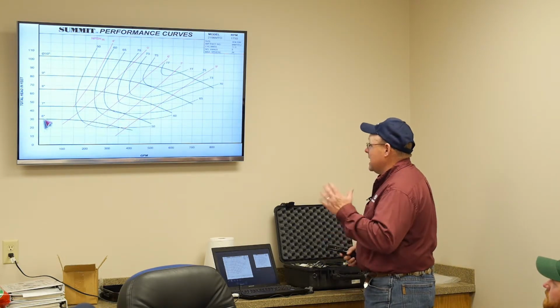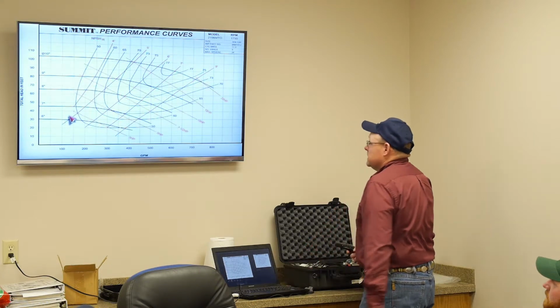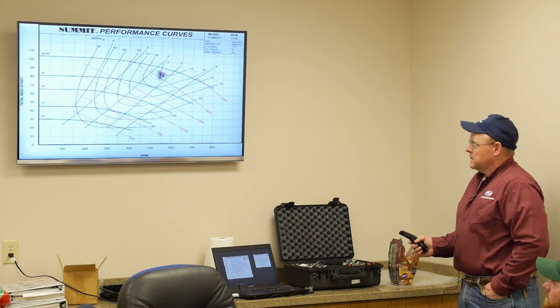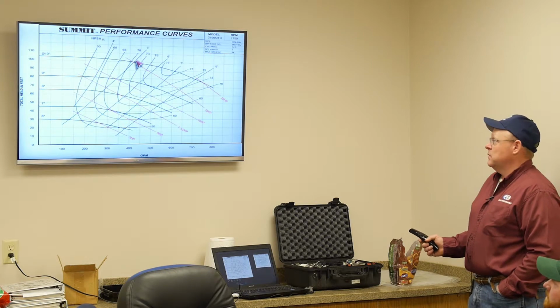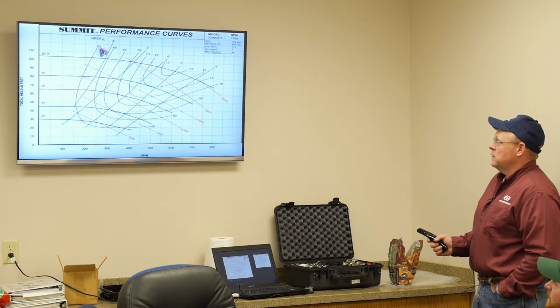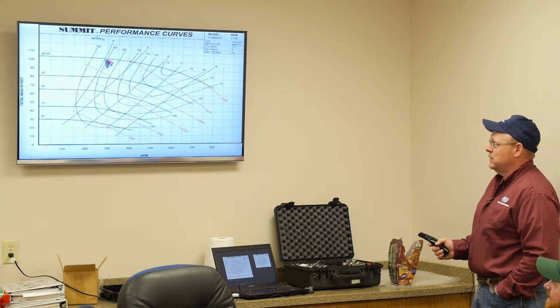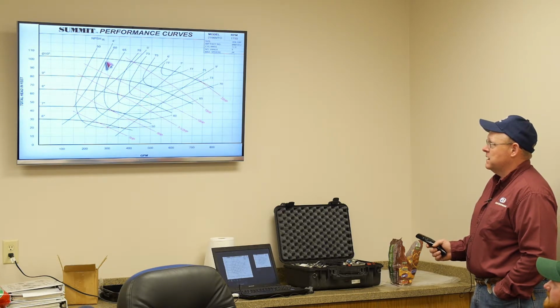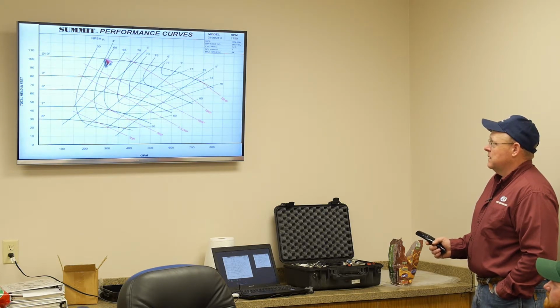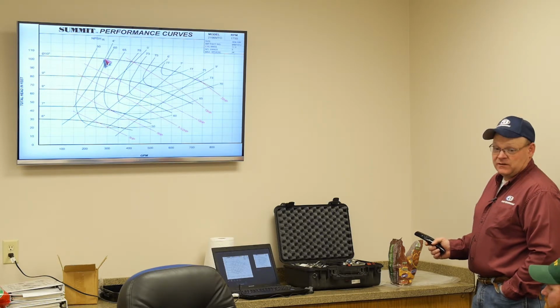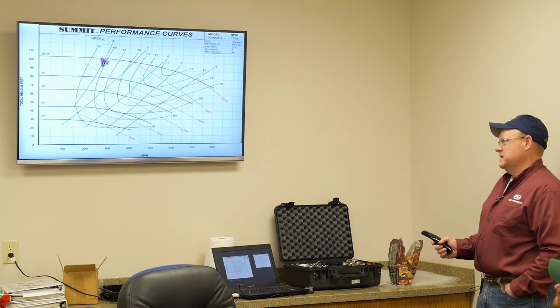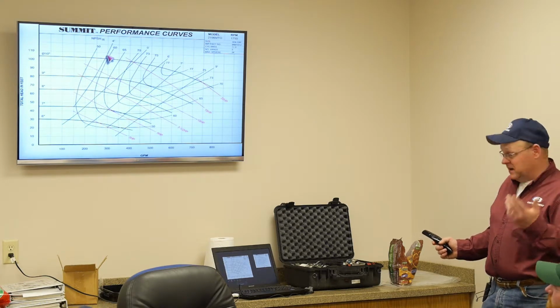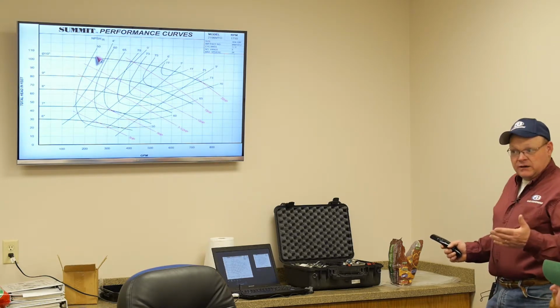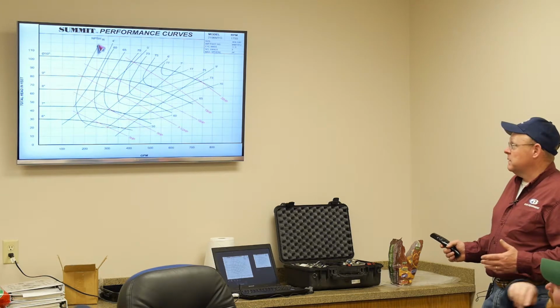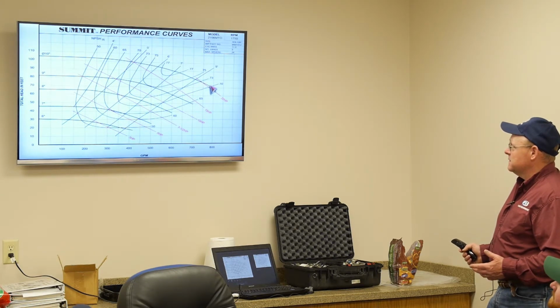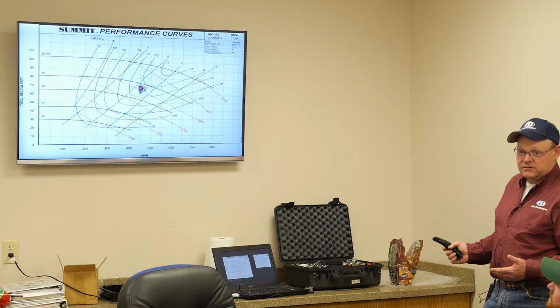Okay, more lines. You ready? Now we got horsepower in there. So if we were over here, see how the horsepower doesn't take many amps, much power to run here? Depending on whose plant it is, you could probably get by with a 10 horsepower with a service factor of 1.15. Not the way we would normally do it, but it could probably run. But if you were out here, you're going to be tripping out that motor.